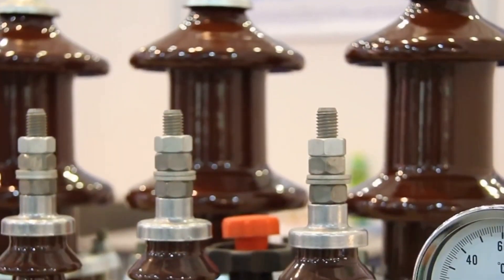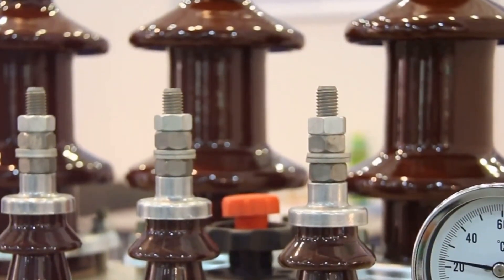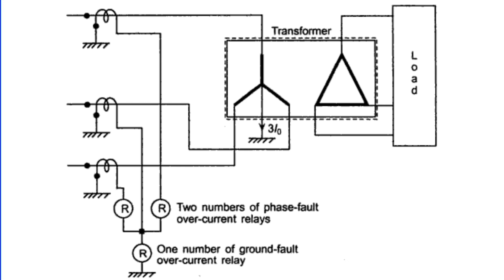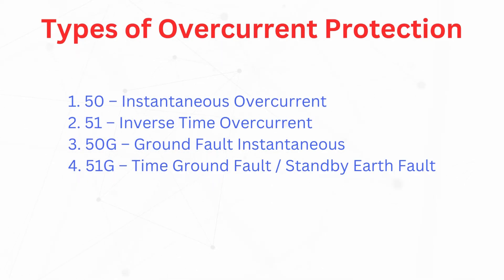Now that we understand the importance of transformer protection, it's time to delve into the different types. First, we have overcurrent and earth fault protection, which acts as a primary or backup protection. This protection kicks into action when the current in any phase crosses the preset maximum value. Its types include instantaneous overcurrent, inverse time overcurrent, ground fault instantaneous, and time ground fault. Each type plays a unique role in guarding against different scenarios of electrical faults, ensuring that any excessive current is detected and dealt with promptly.